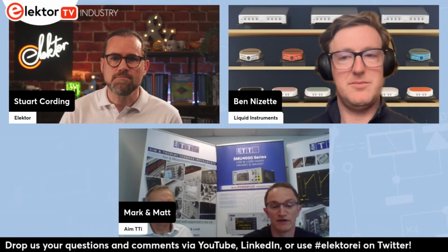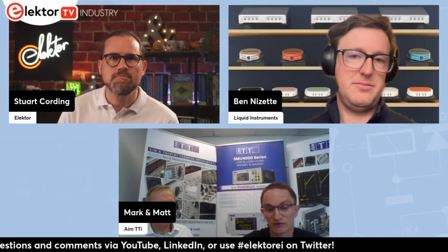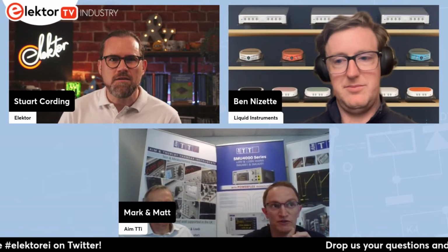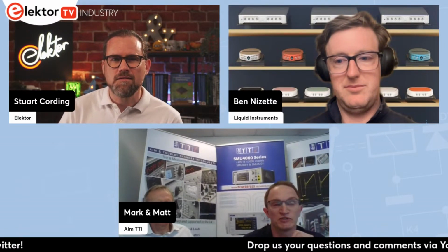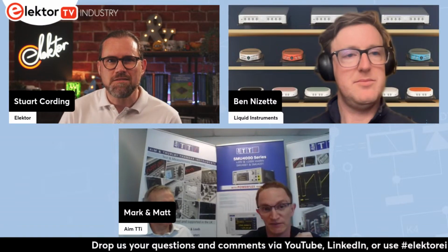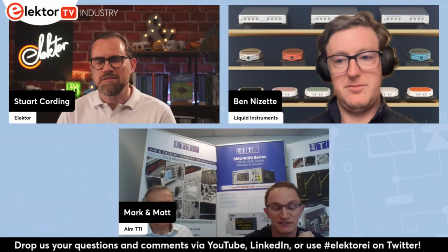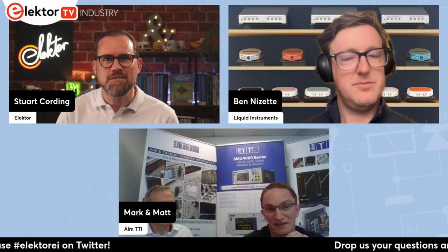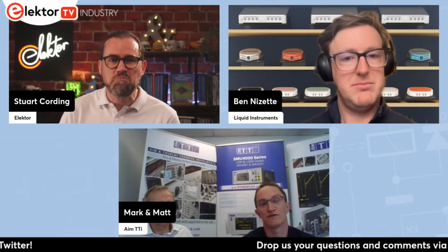Our TestBridge software, SMU TestBridge, allows you to create them. Also, you can export them or import them into TestBridge. We wanted to make it easy for users who have multiple SMUs. If you create a setup in the SMU, you can then store it in that SMU, transfer it to a USB stick, and then take it onto another SMU and import that into that other SMU. Yeah, so it's very transferable.